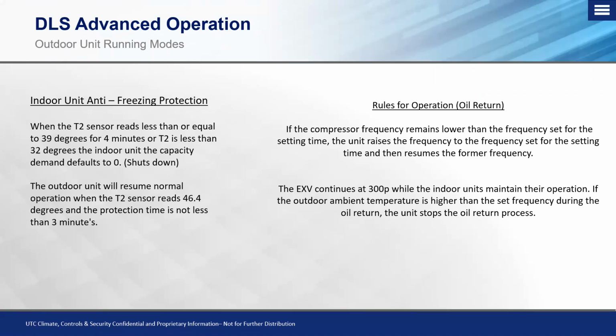So what that really means, and all the mumbo jumbo of that technical description of it, is that when the unit has been running at that target frequency or lower for typically about 30 minutes or more, it's going to adjust its valve positioning and speed up the compressor to try to flush oil back to the compressor for typically about a 3 to 4 minute time period.